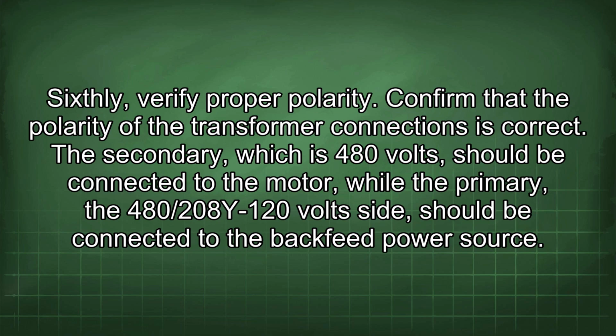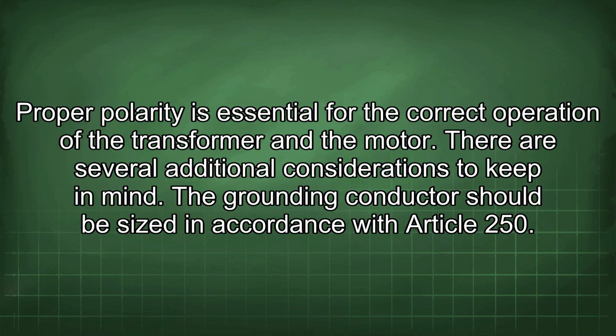Sixthly, verify proper polarity. Confirm that the polarity of the transformer connections is correct. The secondary, which is 480 volts, should be connected to the motor, while the primary, the 480/208Y-120 volts side, should be connected to the backfeed power source. Proper polarity is essential for the correct operation of the transformer and the motor.